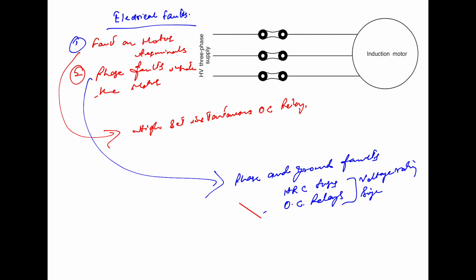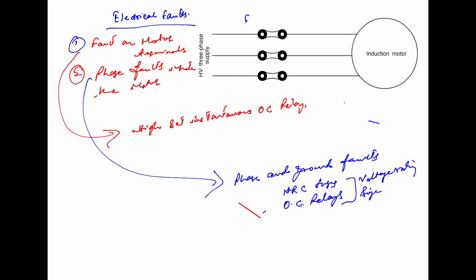Now the figure here shows the HRC fuse protection of the induction motor. Here we will have the high voltage three-phase supply, and here the HRC high rupturing capacity fuses are basically used. In this case, the fusing current should be greater than the starting current of the motor, and the fuse operating time should be less than the permissible locked rotor time of the motor.